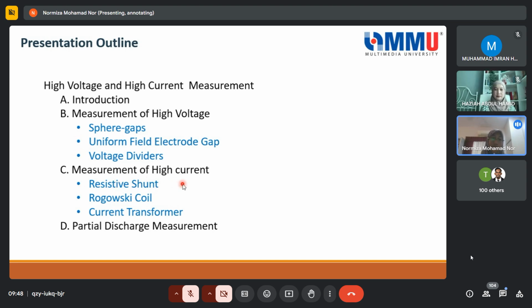And as for the measurement of high current, as I mentioned before, some high voltage labs, understandably, do not have this high current measurement because the equipment being tested are not for current evaluation, but rather for performance, which can simply be observed from the measurement of high voltage, which can be adequate. But anyway, we still have some introduction, just in case in future you come across high current measurement, so you are familiar with these three devices here: resistive shunt, Rogowski coil, and current transformer.